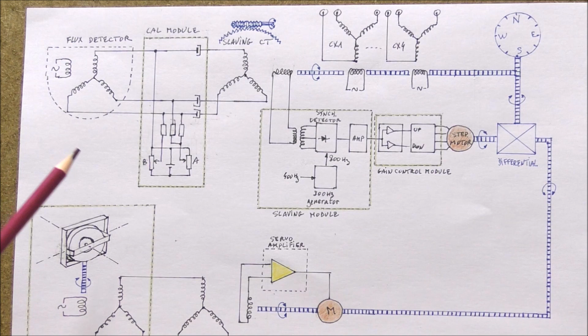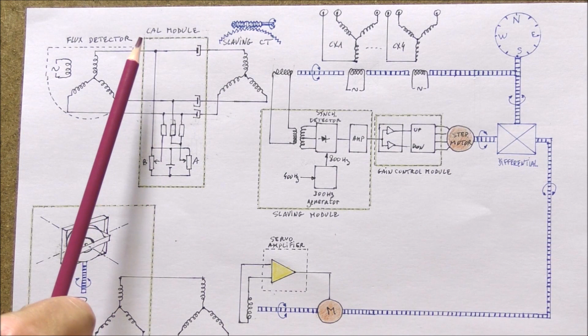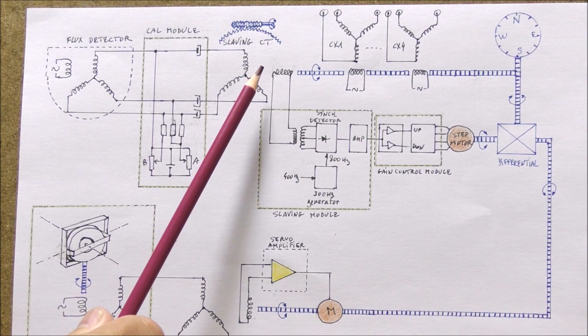The last thing is the calibration module. So the calibration module permits actually to add small DC currents on the coils of the flux gate sensors in order to compensate the static magnetic fields which are present around the flux detector in the aircraft. Also the control transformer which is connected to the flux detector can be adjusted using this helicoidal screw. So this permits to align the result to the flux detector.